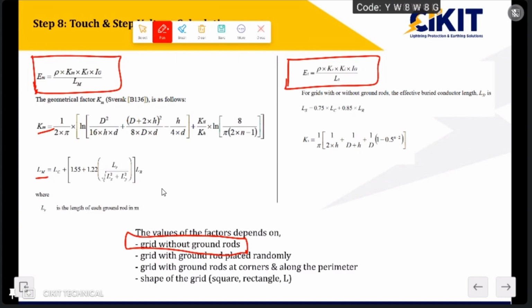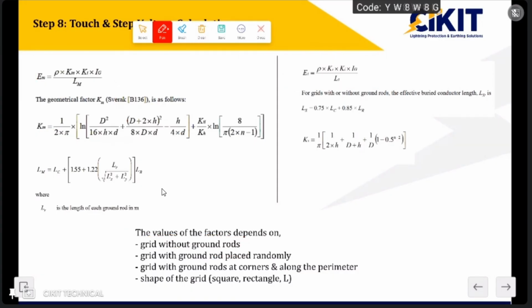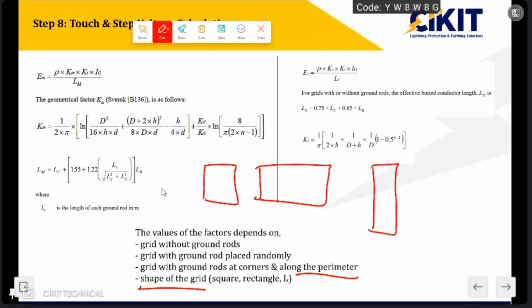So for this particular earth grid, whether we are providing ground rods or not. And second, if I am providing ground rods, whether I am placing the ground rods randomly, or along the perimeter of the grid, or along the corners of the grid. Depending upon the position of the ground rods also, the parameter will be different. And third one is the shape of the grid. They have explained about square configuration, then rectangular configuration, then L shape. Depending upon the shape also, the values of the parameter will be different. So based upon these different parameters, the values of the factors will be different, and the standard has already explained this procedure.